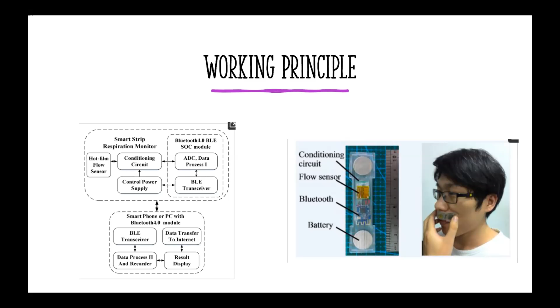The respiratory flow blown out from the nostrils over the strip is detected in real time by the hot film flow sensor attached to the strip. This tube-free configuration makes the respiration monitoring non-invasive and unobstructive to the patient's breath. We chose this module specifically because it's non-invasive and can still provide the optimal results we were looking for.